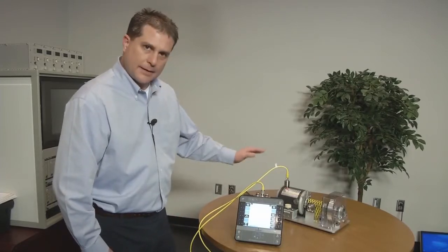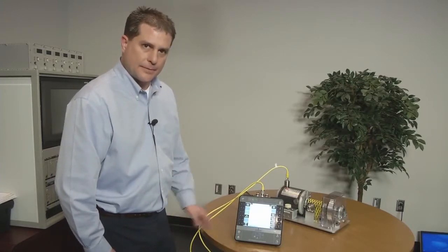So we're good. We're not running this machine at the resonant frequency of 20 hertz. What this test told us was that the energy we were seeing at the one times and two times was not associated with a resonance condition because we've identified the resonant frequency was at 20 hertz. We know our running speed's at 30, so we're not exciting that resonant condition. We've eliminated that as one of our problems with the machinery health.